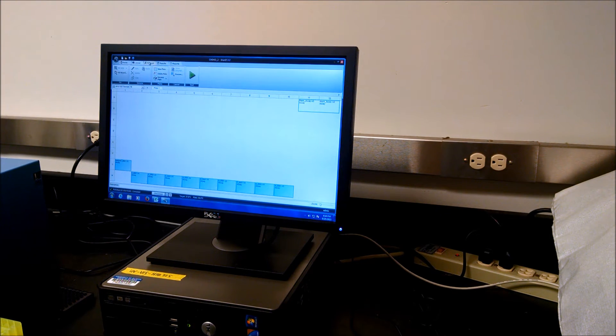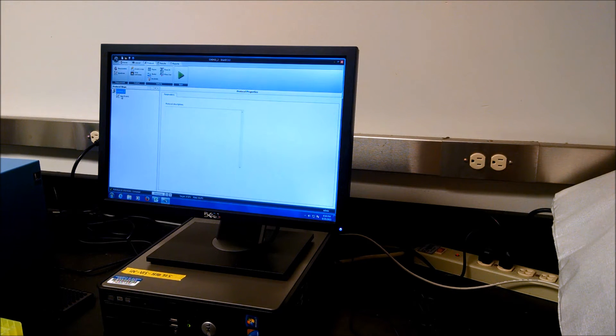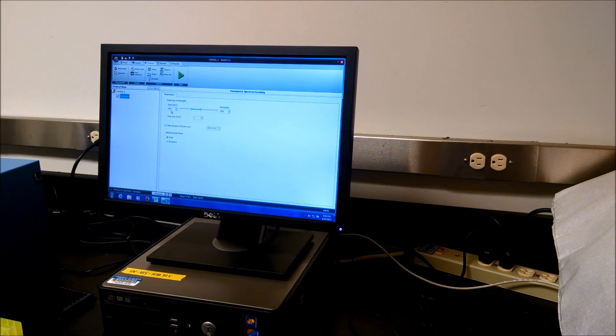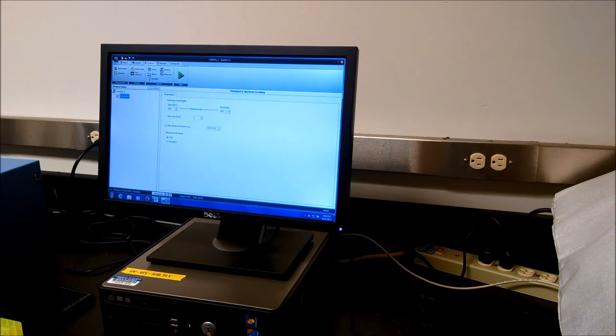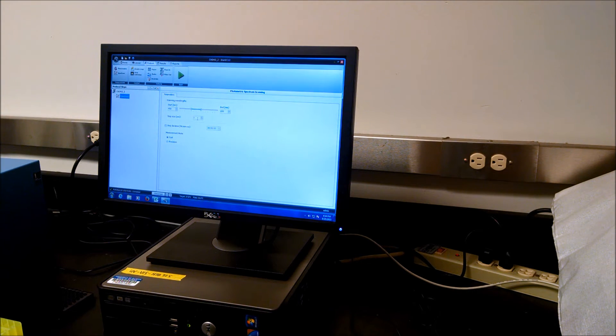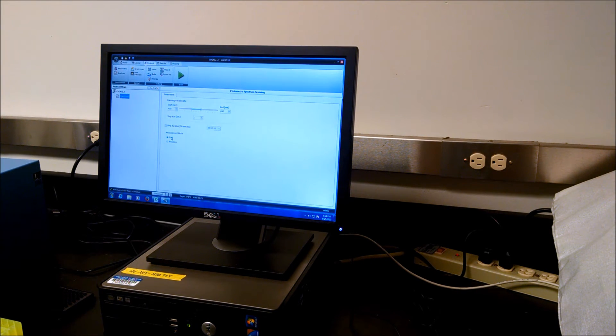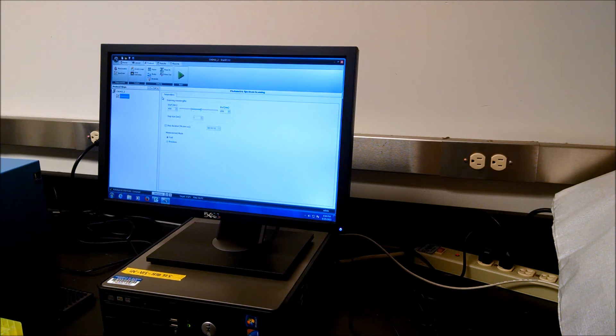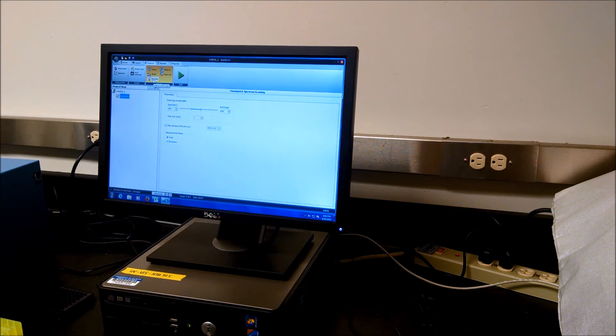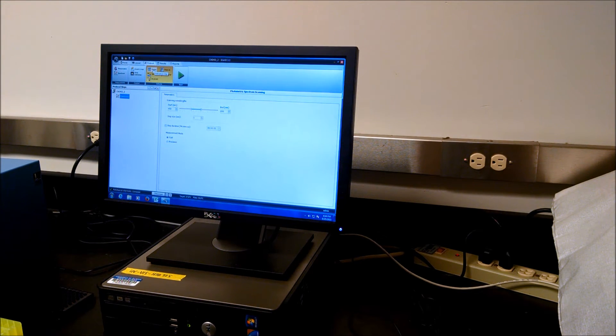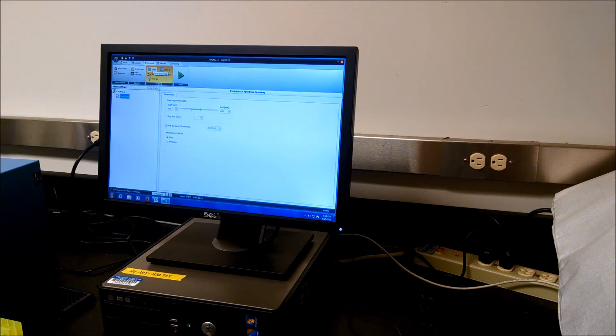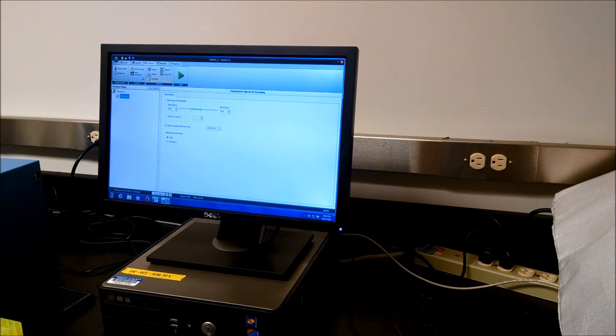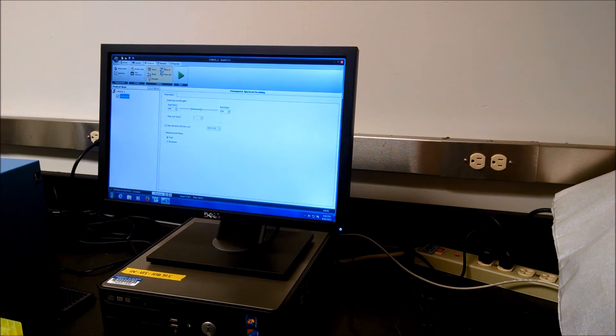Now the protocol I set was to do a scan, to take an absorption spectrum, scan starting at 450 nanometers and ending at 650 nanometers, step at every one nanometer, and I want to do this fast. So this should give decent results for our type of experiment. You see that we could also have it do shaking, we could have it set at a particular temperature to incubate, we could have it scan, pause, scan again, and other protocols we could do with the instrument.